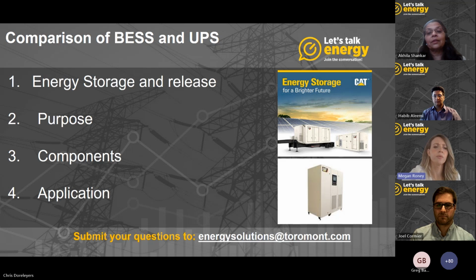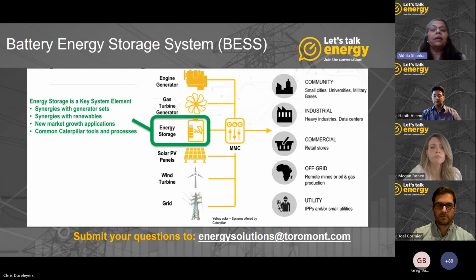Great, thanks, Akhila. So just to summarize, what you're saying is the fundamental difference between a UPS system and a battery energy storage system is a UPS is good for short-term backup power, whereas the BESS is better suited for a high energy density source of power. Yes, that's correct. UPS is good for instantaneous, short-term, limited capacity backup power with zero transfer time during an outage. If we can go to the next slide, we'll be looking at where battery energy storage is a better choice as compared to a UPS.